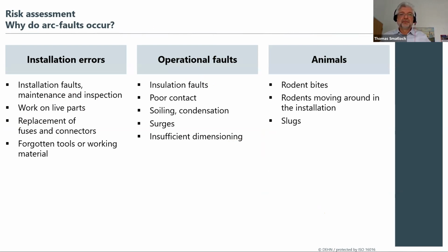Why do typical arc faults occur? Here we have three main reasons, of course: installation errors, operational faults, and animals. Installation faults can happen during maintenance and inspection, when you work on live parts, or you replace some elements within the switchgear cabinets, or you replace fuses or something like this. Very often it happens that tools are forgotten in the installation, and when it comes to vibration, such a tool can fall on live parts, bridge them, and then you can have an arc fault.